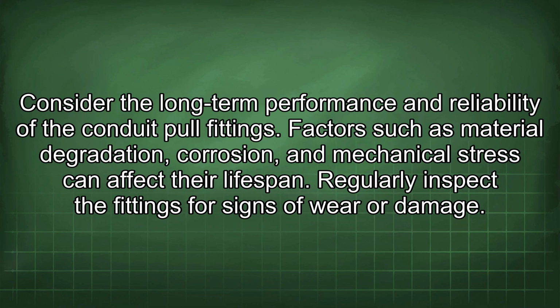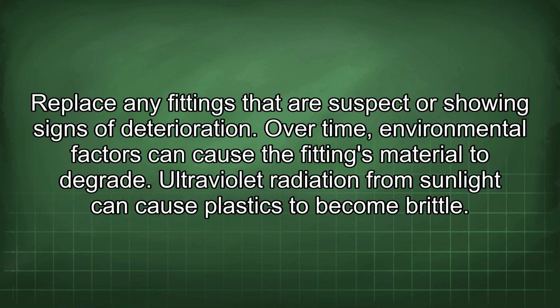Consider the long-term performance and reliability of the conduit pull fittings. Factors such as material degradation, corrosion, and mechanical stress can affect their lifespan. Regularly inspect the fittings for signs of wear or damage. Replace any fittings that are suspect or showing signs of deterioration. Over time, environmental factors can cause the fittings material to degrade.